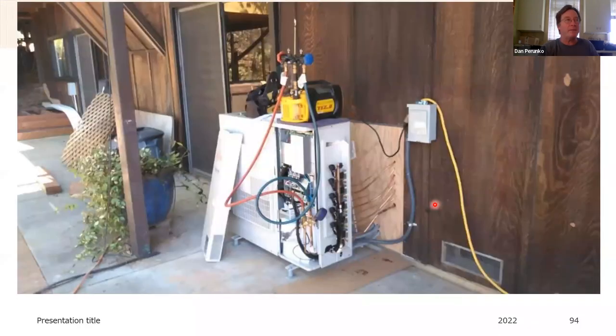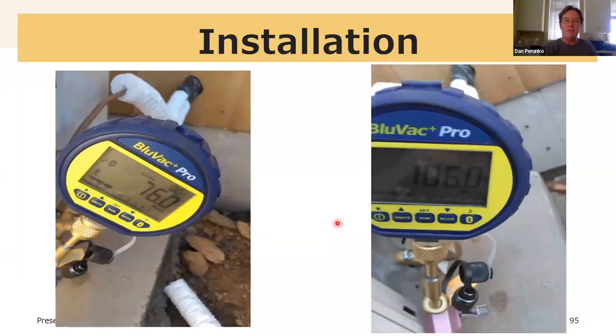We do what's called a vacuum test. This is a vacuum pump. And we're pulling all of the atmosphere out of the line set now. And we pull the vacuum down until it hits a target expressed in microns. You want to be below 200 microns and stable when you shut the pump off. There's a valve right here that isolates the system from that pump. And then you let the gauge sit and you watch it for time.